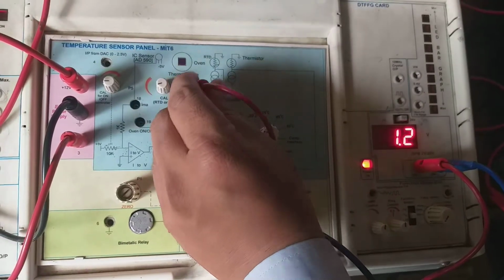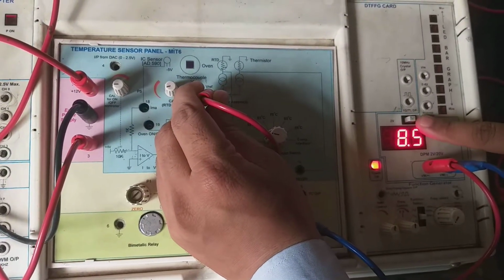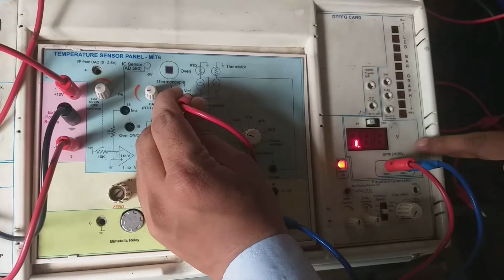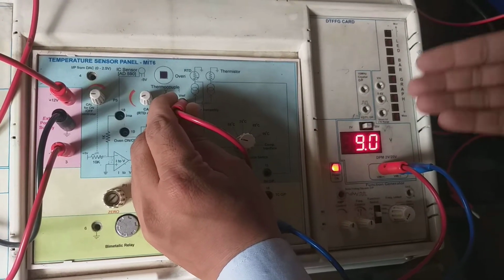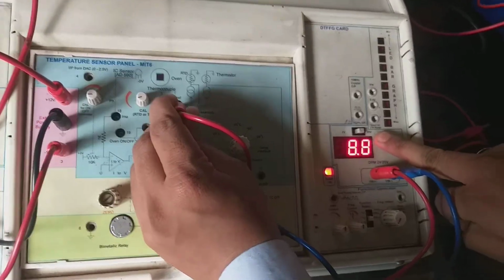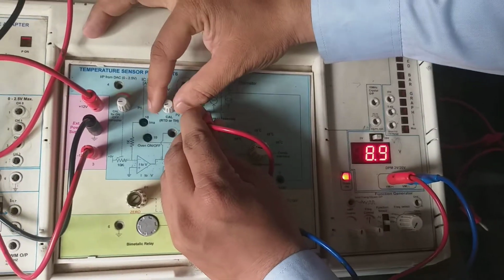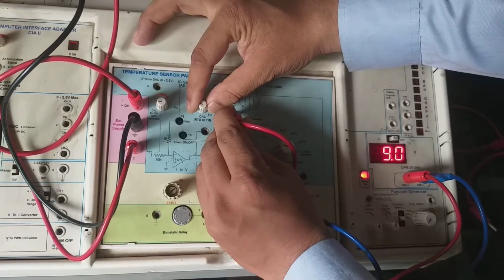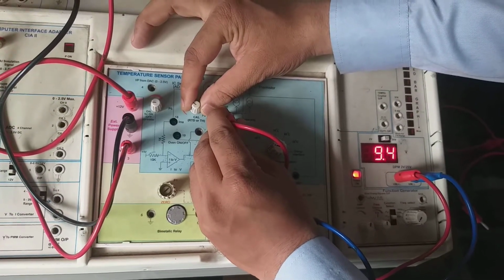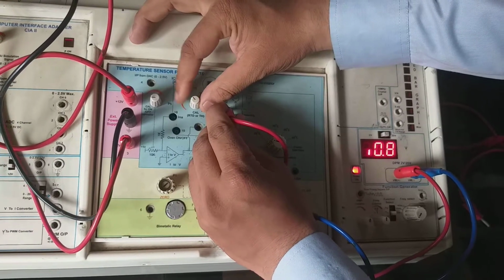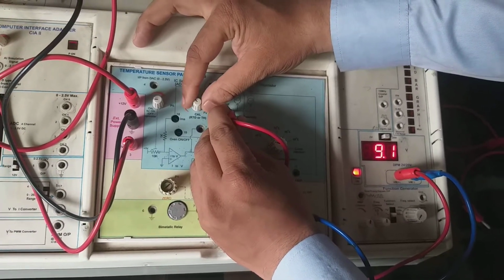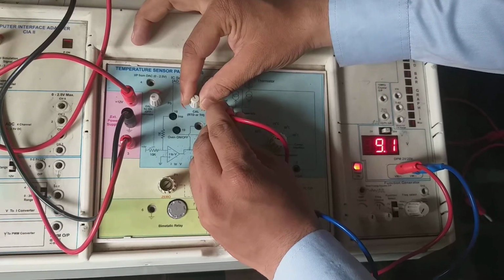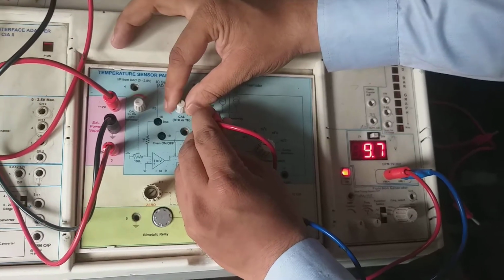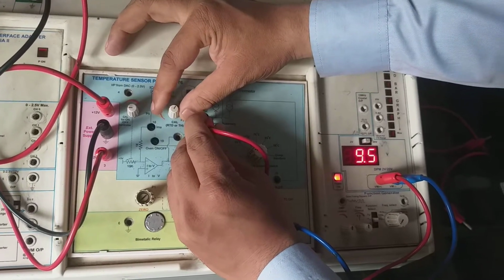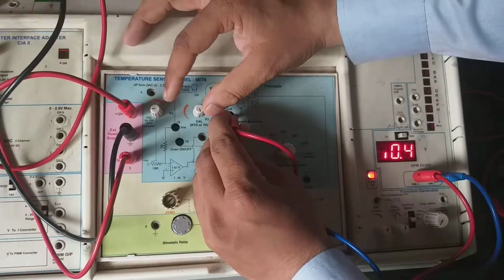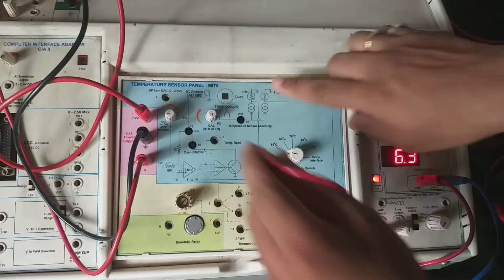Now I can just touch this, and here the two ranges are given. For sensor output, 2 volt is indicated, and if the voltage is greater than 2 volt, then the 20 volt range is to be selected. Now I will move the pot P2 to calibrate it at 10.3 volt. In this way you have to set it to 10.3 over here. And now make sure that the oven is started.